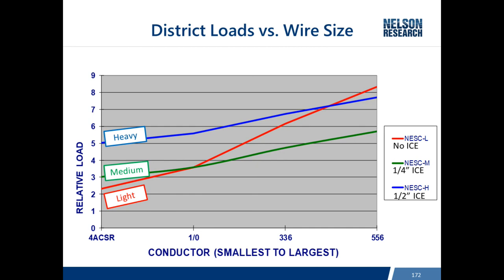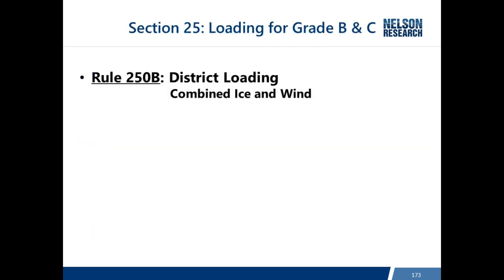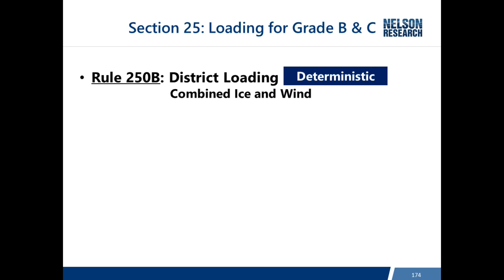Rule 250B district loading is deterministic, meaning it was not based on weather data with a known recurrence probability. It was established by engineers estimating the expected winter storm — for example, half an inch of ice and 40 mph wind in Pennsylvania's heavy loading district. Because these are deterministic loads, the load factor and strength factors differ from the next two load cases, which do have a known probability of occurrence.